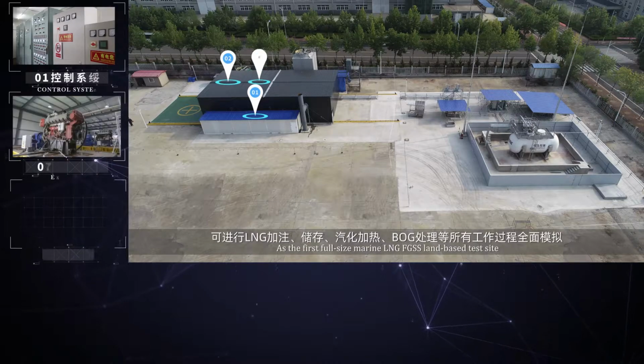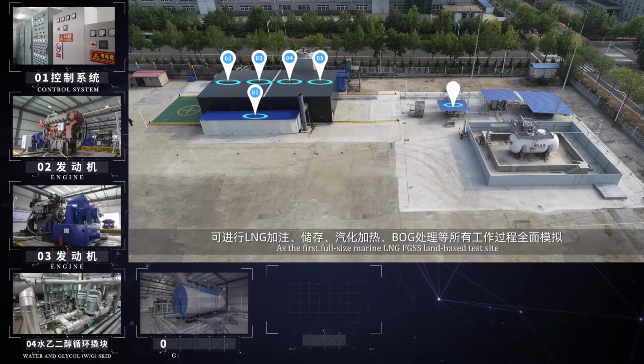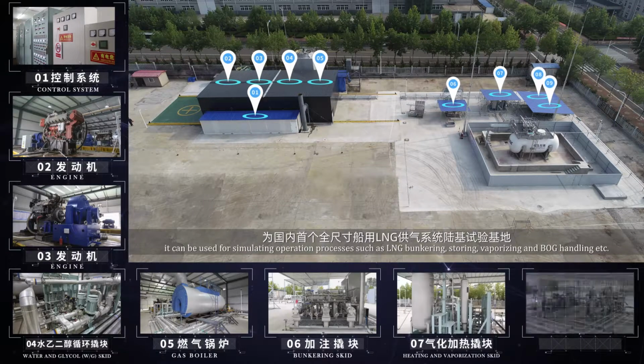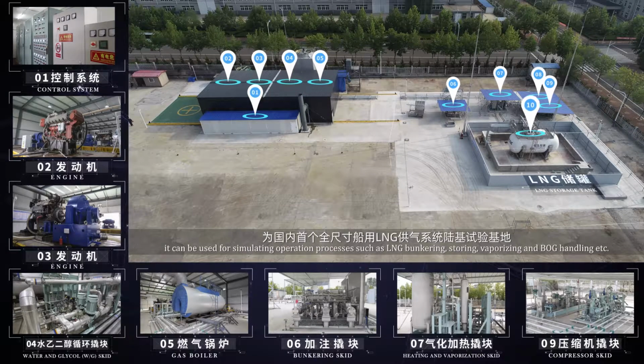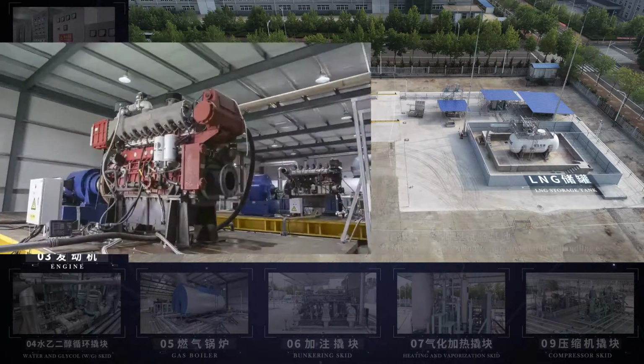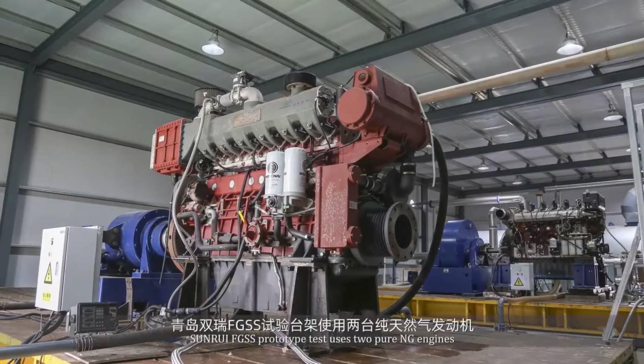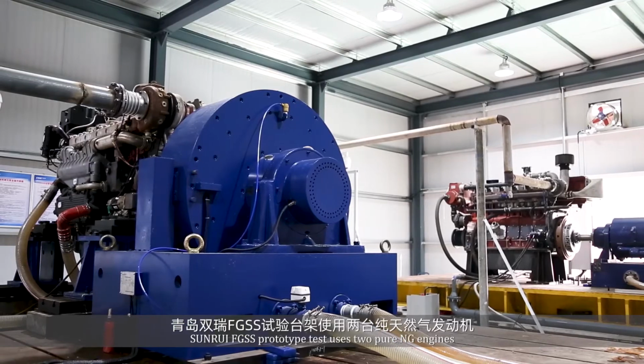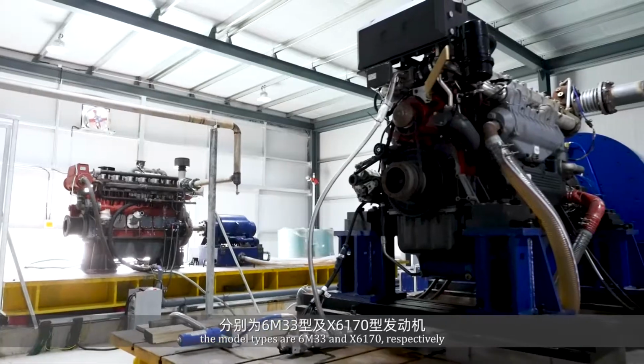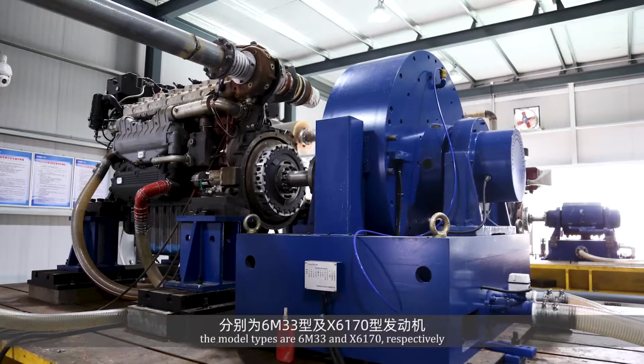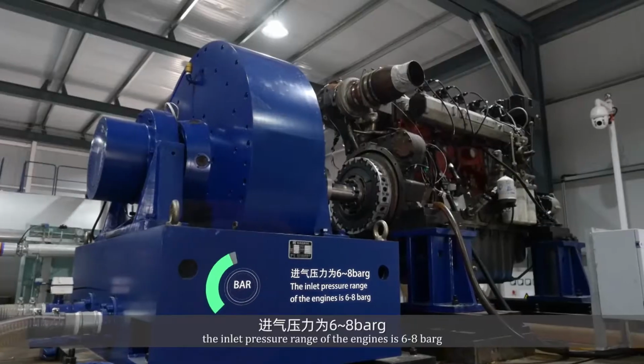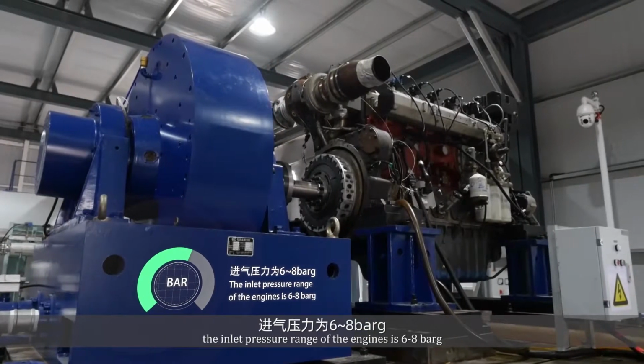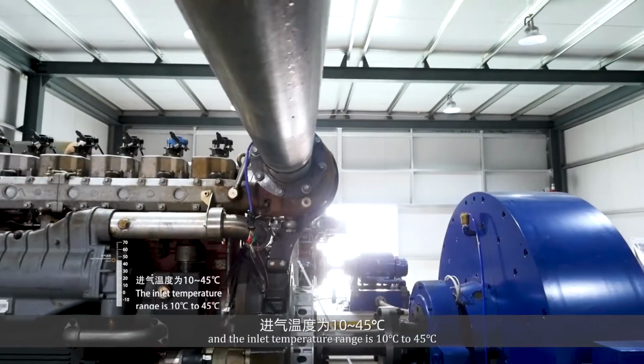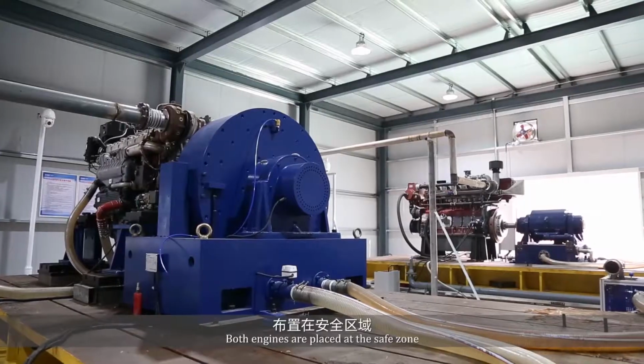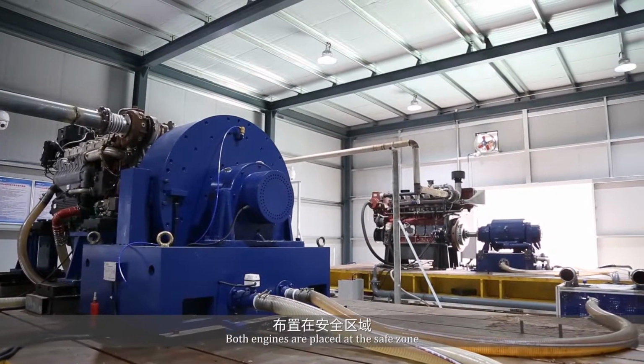As the first full-size marine LNG FGSS land-based test site, it can be used for simulating operation processes such as LNG bunkering, storing, vaporizing, and BOG handling, etc. The SunRui FGSS prototype test uses 2 pure NG engines. The model types are 6M33 and X6170 respectively. The inlet pressure range of the engines is 6 to 8 bar, and the inlet temperature range is 10 to 45 degrees. Both engines are placed at the safe zone.